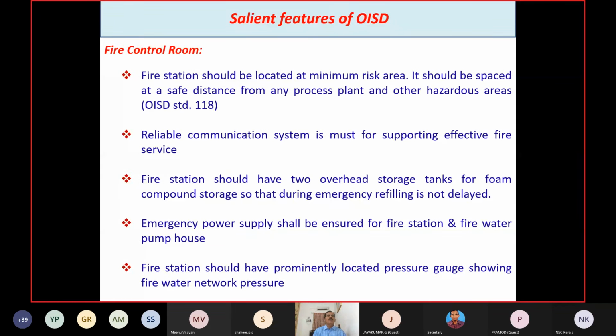And the fire control room, fire station should be located at a minimum risk area. It should be spaced at a safe distance from any process plant and other hazardous area. In standard 118 it has also been clearly mentioned. And a reliable communication system is a must for supporting effective fire service. And the fire station should have 2 overhead storage tanks for foam compound storage, so that during an emergency refilling is not delayed. Emergency power supply should be ensured for the fire station and fire water pump house. The fire station should have a prominently located pressure gauge showing fire water network pressure.